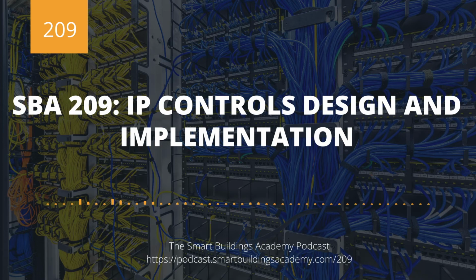If you lose a controller in the middle of the daisy chain, every controller after that you'll be unable to reach. Which brings us up to the ring architecture. Now, the ring architecture actually enables us to use two switch ports, one for one side of the ring and the other for the ending side of the ring. And then the controllers are wired up using a daisy chain. If one controller goes down and you can't reach the other controllers, then the other port will start communicating. Now, there's all this stuff about rapid spanning tree and blocking ports and open ports.